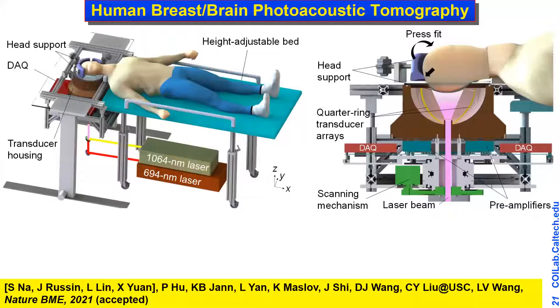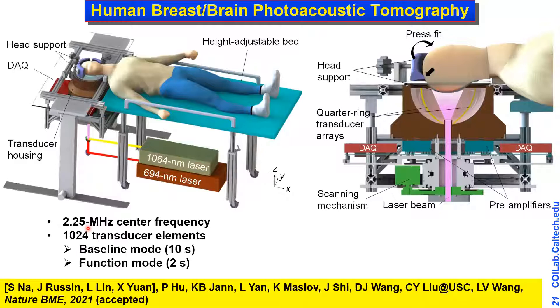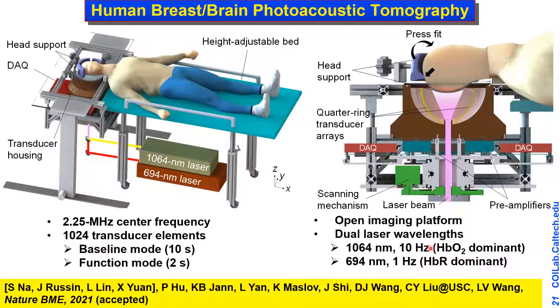We developed a next-generation imaging system with isotropic resolution using a hemispherical structure with 1,000 transducer elements. For breast imaging we use 2.25 MHz centered ultrasound frequency. For functional brain imaging the baseline mode is 10 seconds and functional mode is only 2 seconds. This is an open imaging platform using dual laser wavelengths to quantify both oxyhemoglobin and deoxyhemoglobin concentrations.